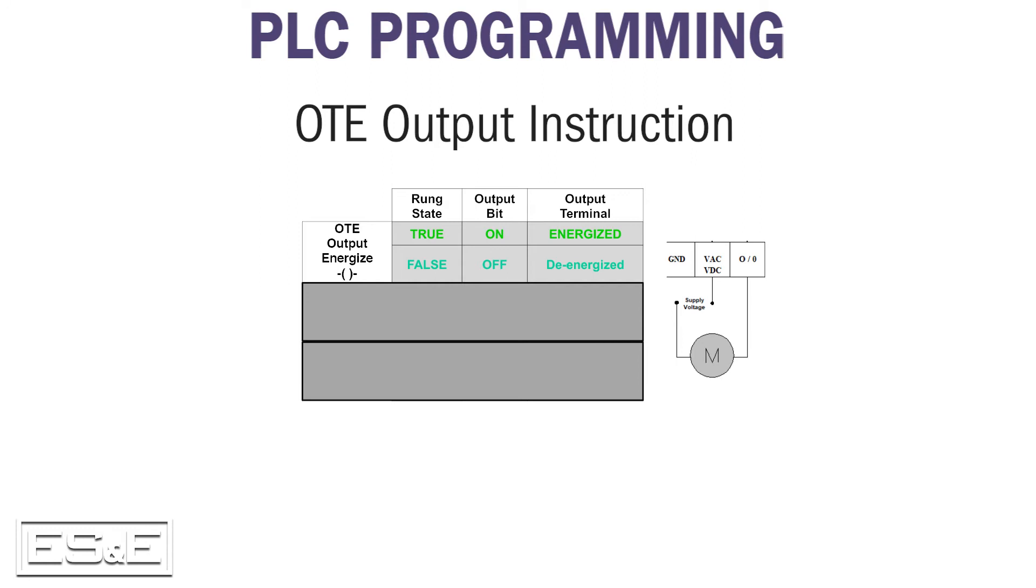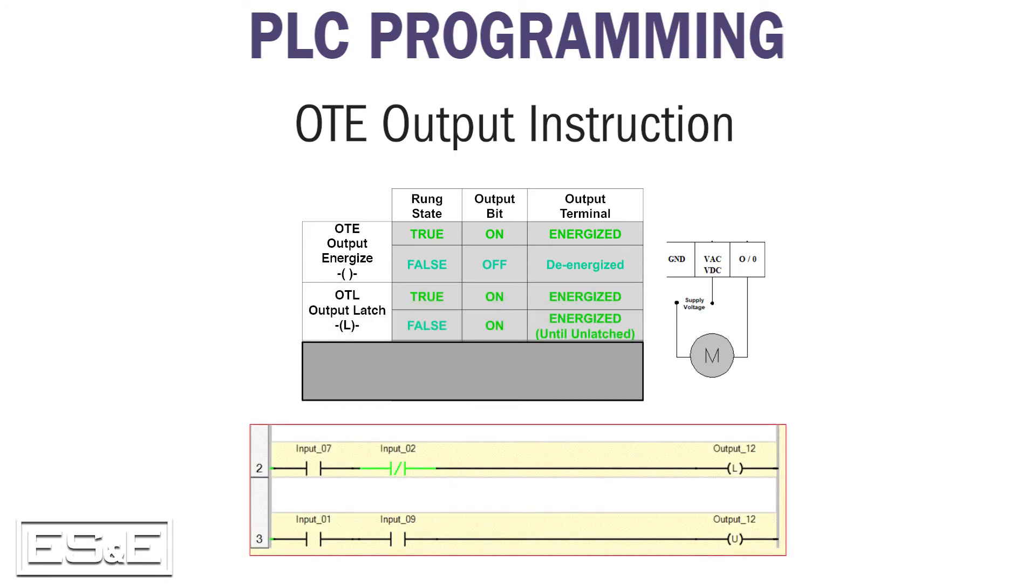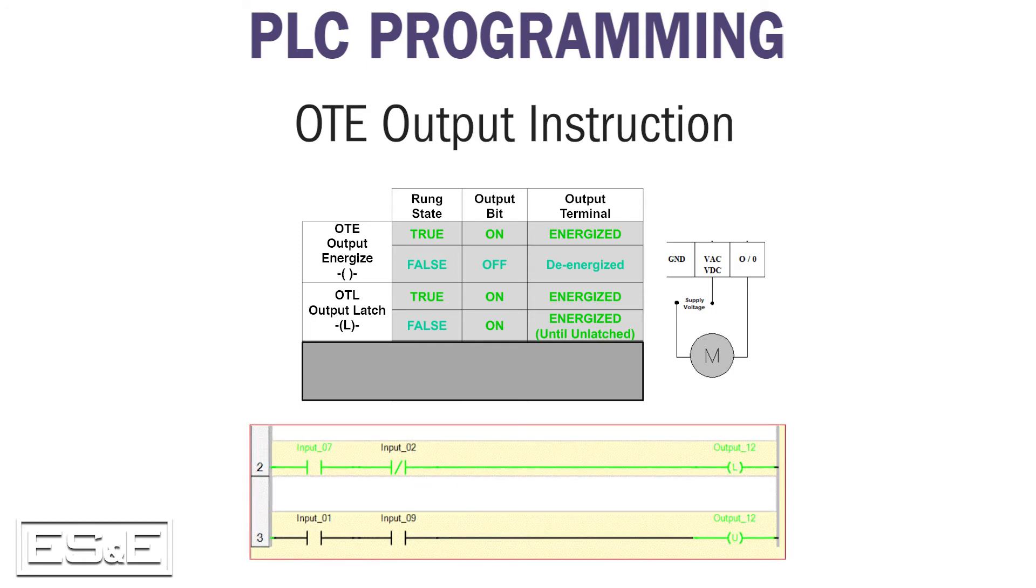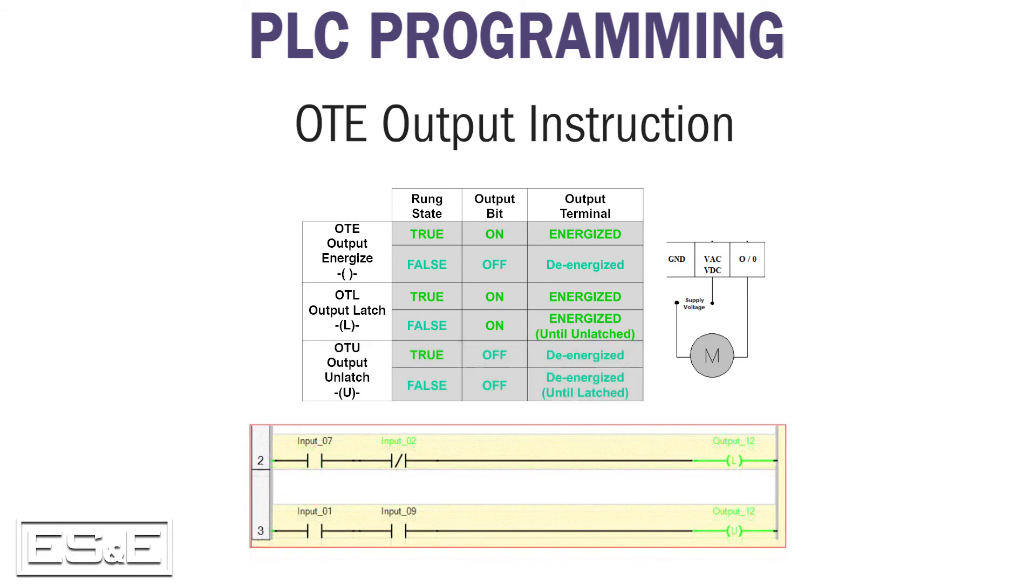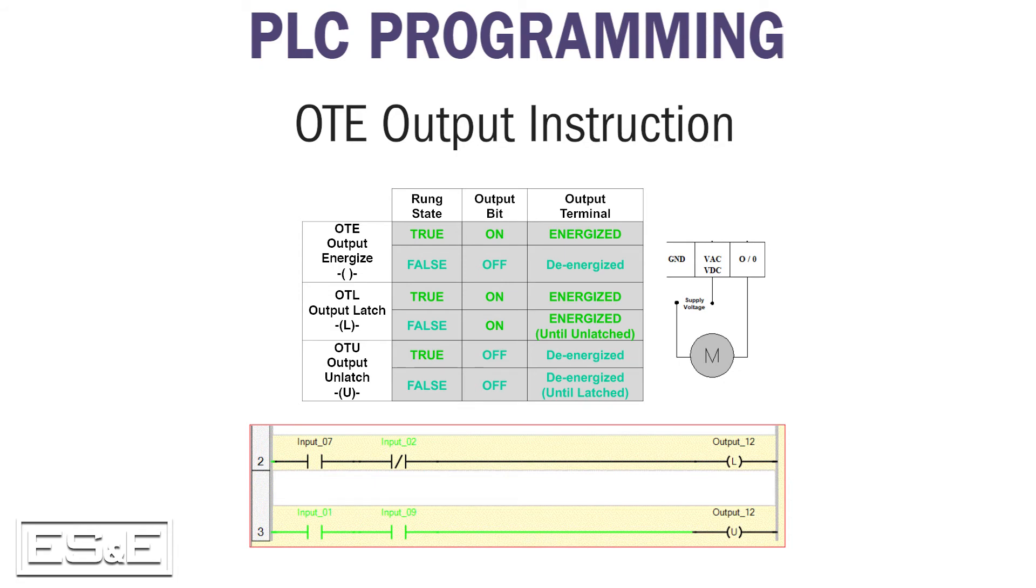There are two other output instructions worth noting. The output latch, or OTL, allows a rung of ladder logic to solve true and turn the output on. In subsequent scans of the logic, the rung can solve false, but the output will continue to stay on. To turn off the OTL, an output unlatch, or OTU instruction is used in a different rung. When that rung solves true, the OTU will turn on and unlatch the original OTL. At that point, the output will turn off.